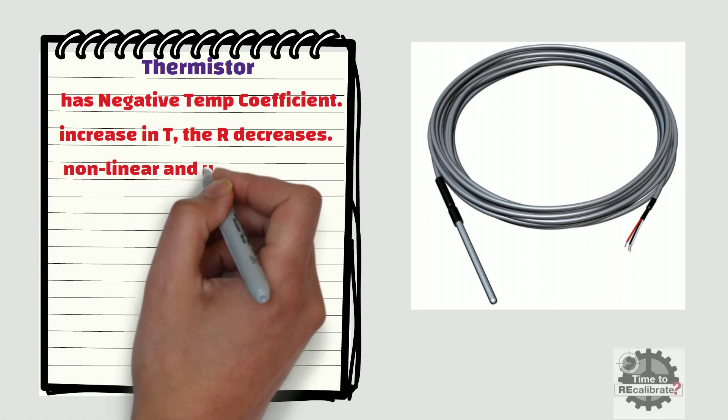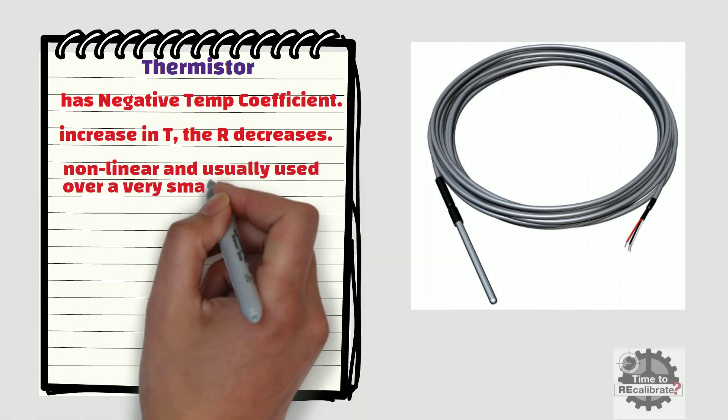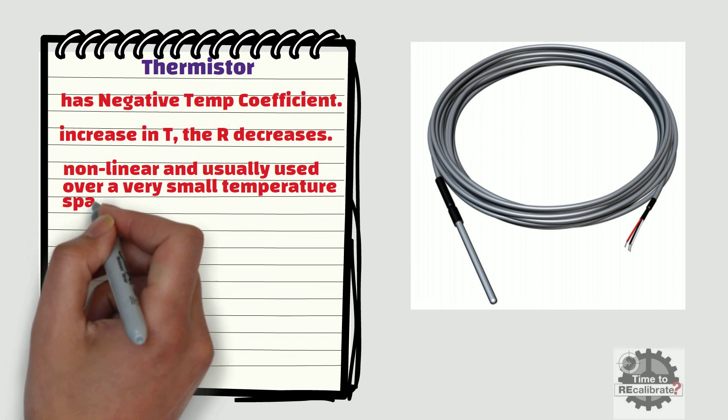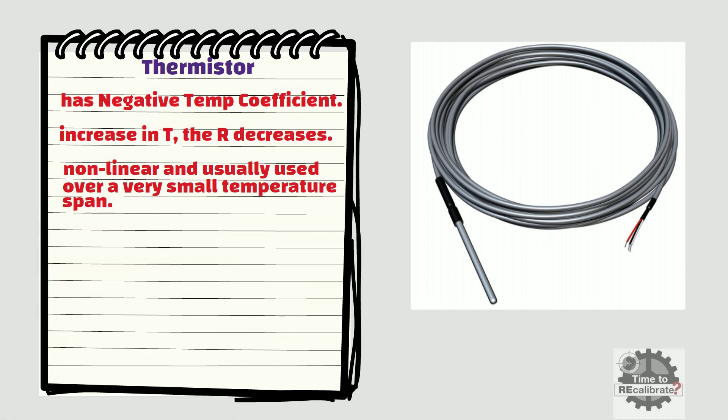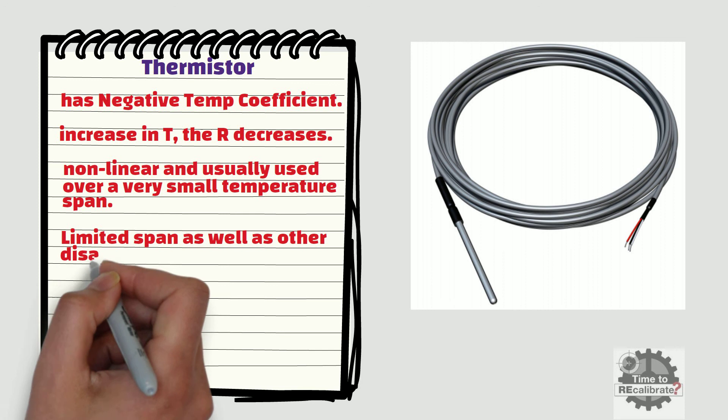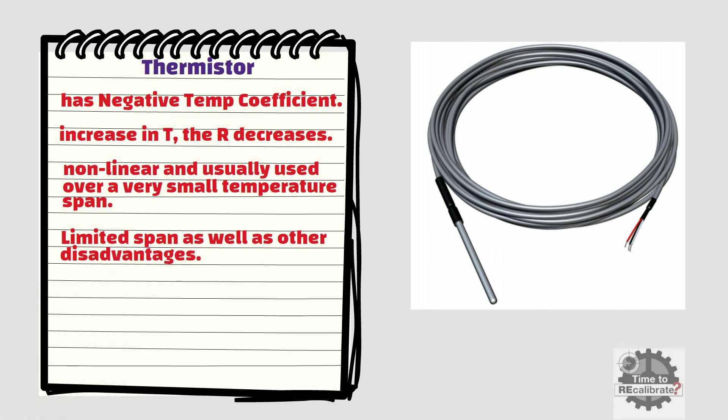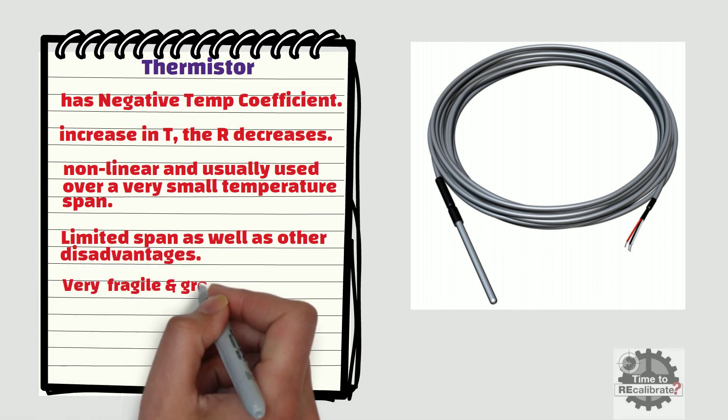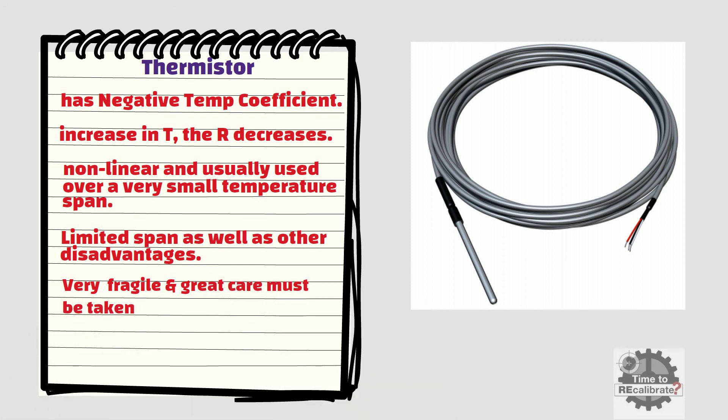Although the thermistor is a more sensitive device, it is also very non-linear and usually used over a very small temperature span. Thermistors have not gained nearly the popularity of RTDs or even thermocouples in industry due to their limited span as well as other disadvantages. Thermistors are quite fragile and great care must be taken to mount them so they are not exposed to shock or vibration.